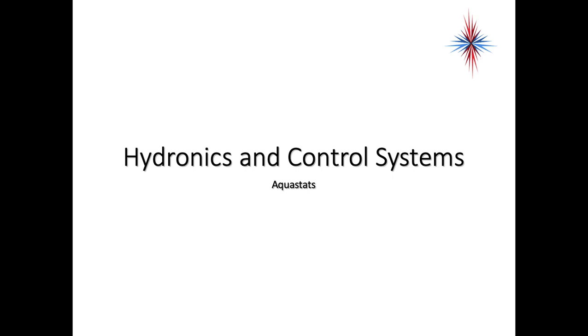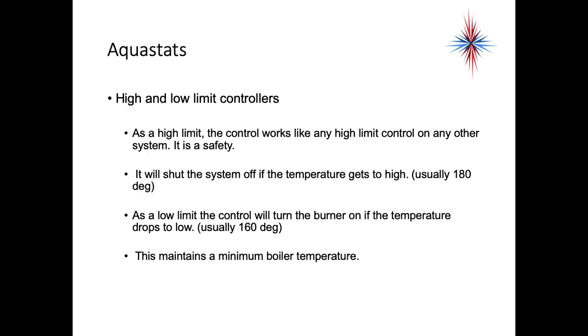In this video we're going to continue our conversation about hydronics and control systems by talking about aquastats. Aquastats are high and low limit controllers in a heating hydronic system. As a high limit control, it works like any other high limit controller — it's a safety that will shut the system off if the temperature gets too high, usually about 180 degrees.